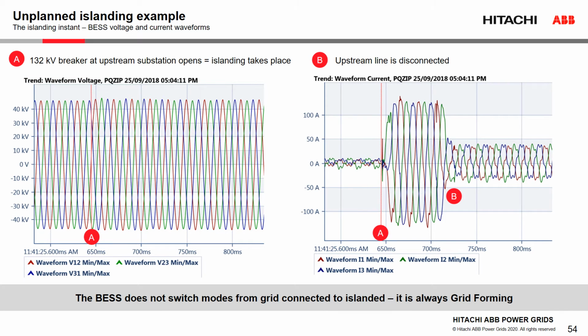Here we see the current and voltage waveforms from the sequence just described. On the left, we see the voltage waveform at the 33 kV bus, and on the right, we see the current waveform output from the grid-forming converter. On the left, we can see throughout the sequence, the voltage waveform remains constant. There is no notching, interruption, or distortion.